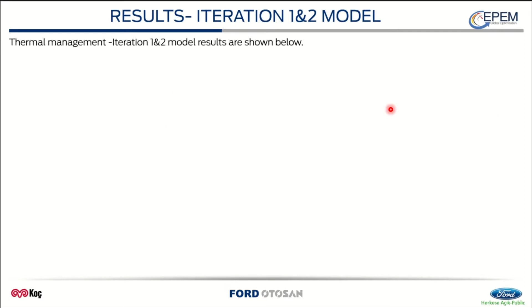Due to decreased volume flow rate, e-motor inlet temperature increases in iterations 1 and 2 compared with the reference model results. In the next iterations, water pump power and radiator cooling capacity should be updated to meet flow rate and temperature targets.